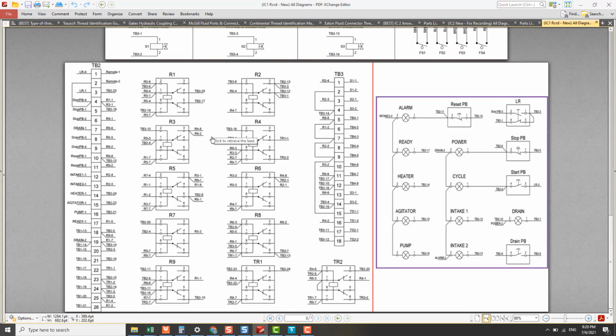That means this point 19 here has a slightly loose connection, or a load with slightly high resistance. You can treat the slightly loose connection as a load here. So when you measure the voltage here, the current flowing through this path is divided into two paths, one to the load and the other to the multimeter. The multimeter will register voltage, but it will be lower than 230 volt AC. Similarly here, point 14.